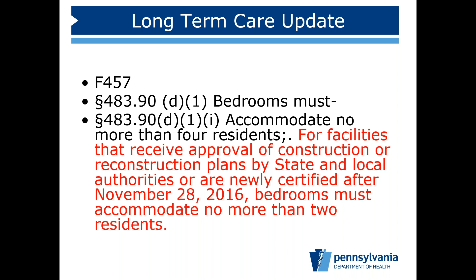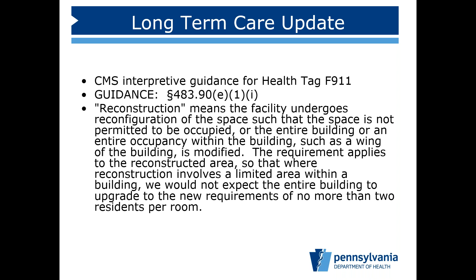So their definition of reconstruction, this is coming right from Health Tag F911, talks about undergoing the reconfiguration of the space such that the space is not permitted to be occupied, or the entire building or entire occupancy within the building is modified. And then the requirement only applies to the reconstructed area. So if you have 4 wings and you decide to just renovate one, it only applies to that area you're renovating. It doesn't mean you have to go renovate the other 3 wings as well. It just applies to the area being renovated.